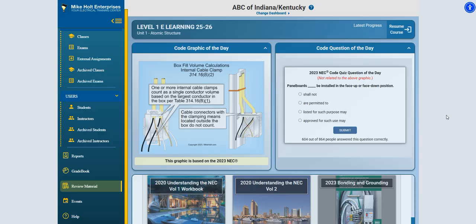Keep in mind when you're calculating box fill, your equipment grounding conductors, up to 4 conductors, are calculated as 1. So that would be 2.00 cubic inches. As you see in the box there, you have 2 hot wires, or 2 blacks and 2 whites. So each one of those, that's going to be a total of 8 cubic inches. Your equipment grounding conductor, so that makes it 10. You've got an internal clamp, so that's going to be 2 more. So that's going to be a total of 12 cubic inches in that box.